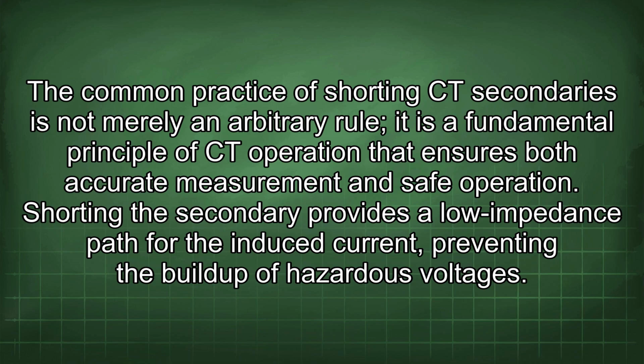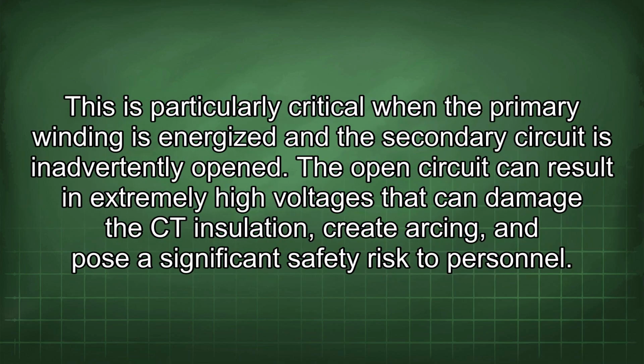The common practice of shorting CT secondaries is not merely an arbitrary rule, it is a fundamental principle of CT operation that ensures both accurate measurement and safe operation. Shorting the secondary provides a low impedance path for the induced current, preventing the buildup of hazardous voltages. This is particularly critical when the primary winding is energized and the secondary circuit is inadvertently opened.